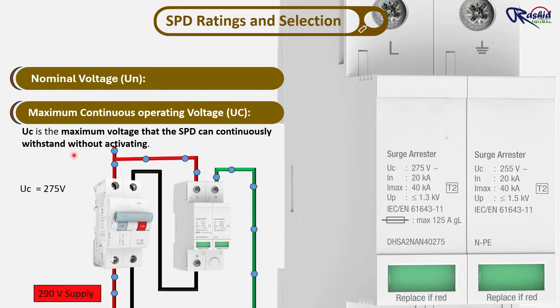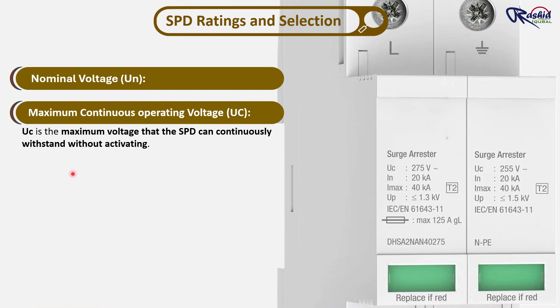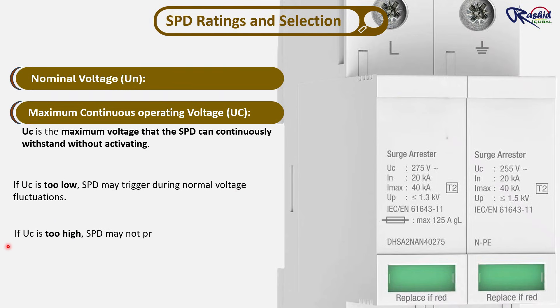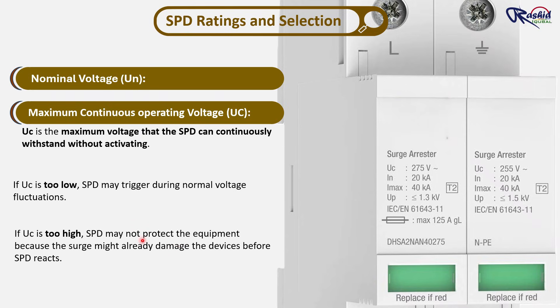For slow or continuous overvoltage, you need an overvoltage protection relay. The UC rating is important: if it is too low, the SPD may trigger during normal voltage fluctuations. If the UC rating is too high, the SPD may not protect the equipment because the surge might already damage the devices before the SPD reacts.